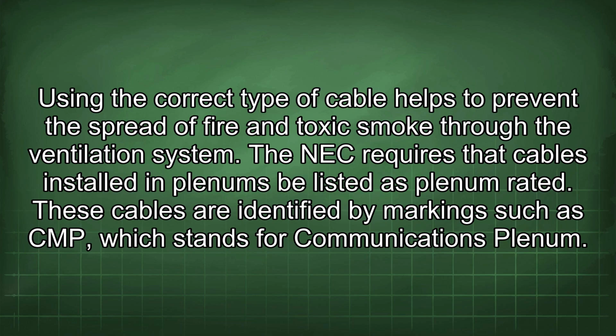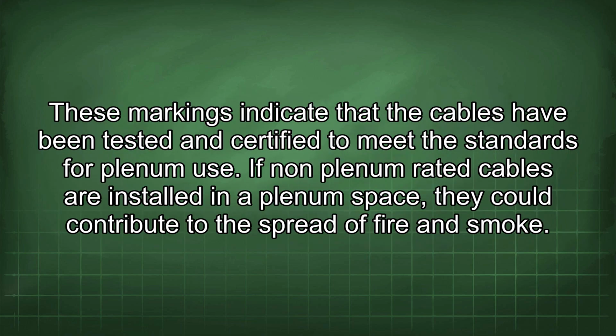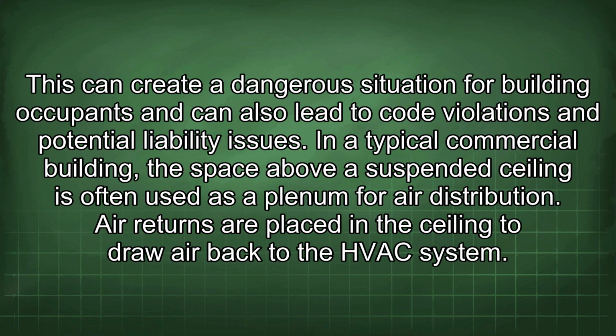The NEC requires that cables installed in plenums be listed as plenum-rated. These cables are identified by markings such as CMP, which stands for Communications Plenum. These markings indicate that the cables have been tested and certified to meet the standards for plenum use. If non-plenum-rated cables are installed in a plenum space, they could contribute to the spread of fire and smoke. This can create a dangerous situation for building occupants and can also lead to code violations and potential liability issues.